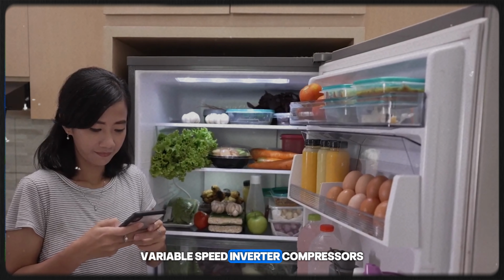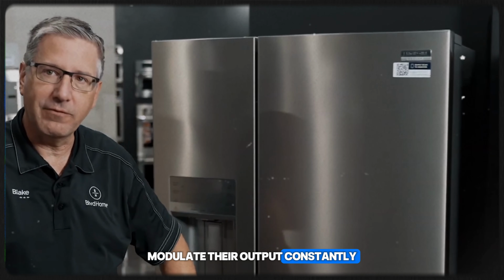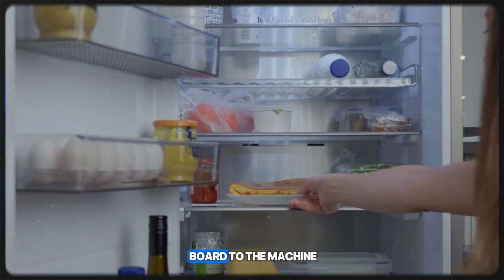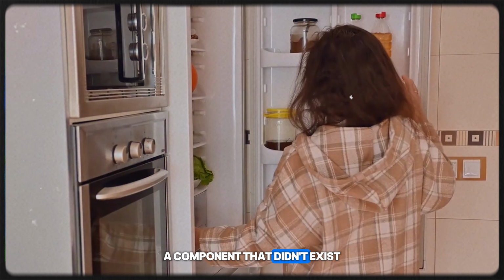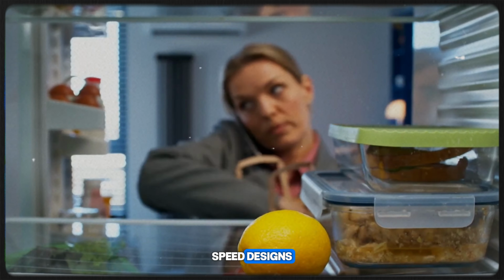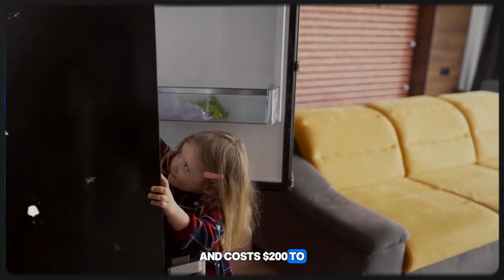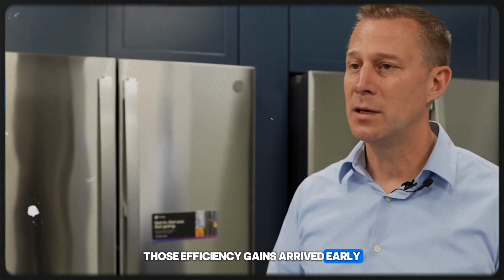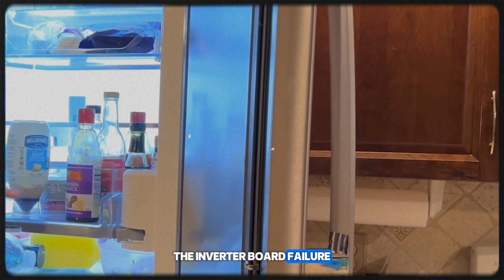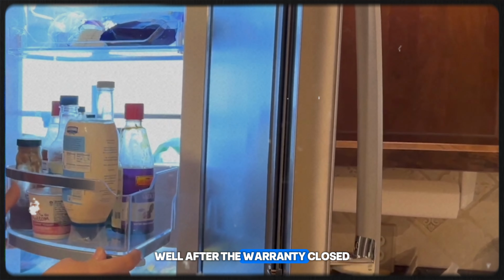Variable speed inverter compressors modulate their output constantly to match the cooling load, which saves electricity but adds an inverter board to the machine. A component that didn't exist in single-speed designs and costs $200 to $500 to replace. Those efficiency gains arrive early. The inverter board failure arrives at year 6, well after the warranty closed.